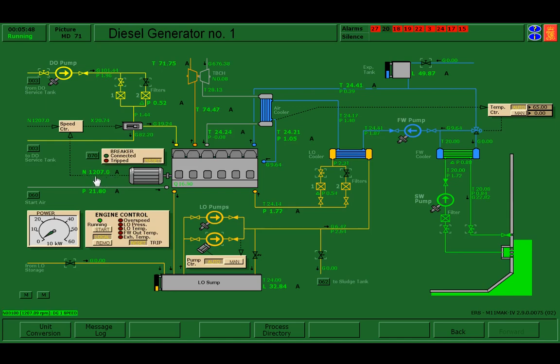He appears to be started, so my speed is stabilized around 1200 RPM. I'm going to just double check a couple things before I move on. One, I do have flow of cooling water. I also have flow of cooling water into my engine, and my fuel looks like it's flowing, which means that I think all of my systems are functioning correctly. My lube oil tank level is constant, so if it's going up or down, then it's likely that you are either losing oil to the sludge tank or you have forgotten to close off your supply valve.